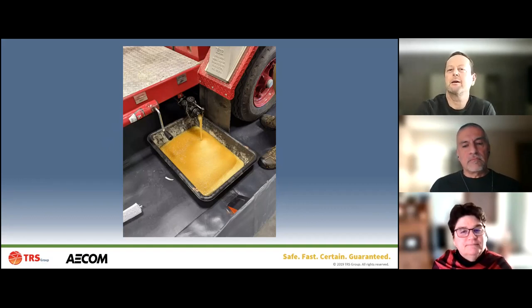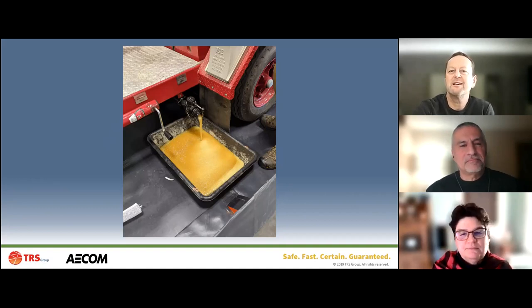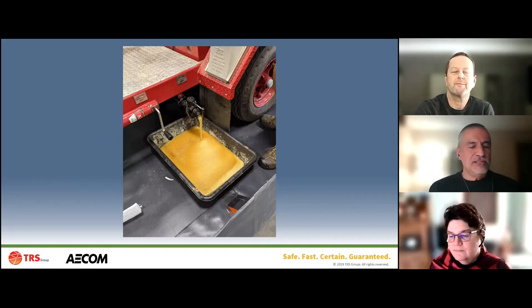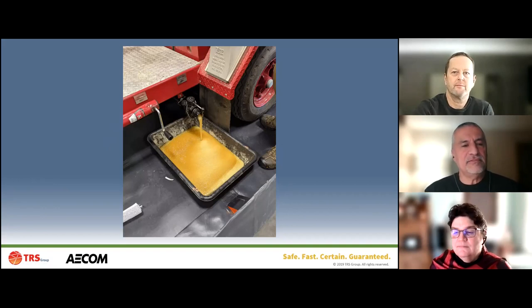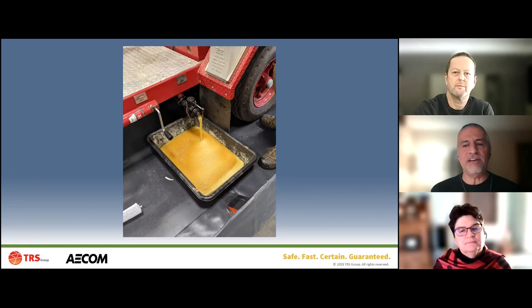The product we use for cleaning AFFF out of firefighting vehicles is called Perfluorad, created and developed by Cornelsen in Germany. TRS is the exclusive licensee in North America. Perfluorad is a biodegradable active liquid - it gets dosed into PFAS-contaminated water, creates ionic bonds with the PFAS, and then creates flocs. That's the quick version of how Perfluorad works.